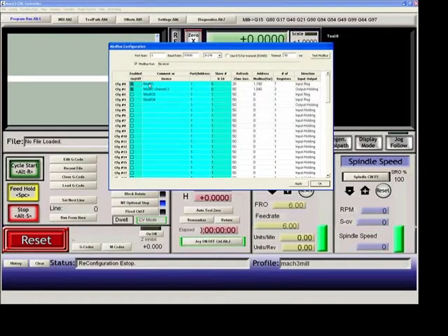I've given it a name of Mod I/O. These names are usually read by a plugin, and they're really just there as a notification of what you're using it for. I only have two configurations turned on. They're both set to port 1. So that's serial port 1. Slave number 6, which my Mod I/O happens to be set to as a slave number. Yours will probably be a 1 or whatever your slave number is for your Modbus.